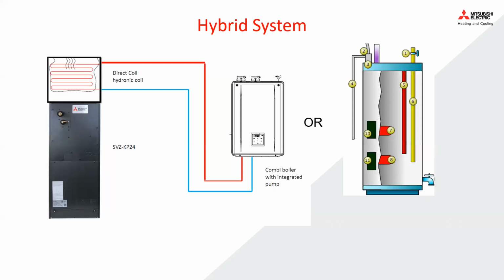So I have a builder up in Ottawa. This is their standard go-to, where they have a hydronic coil placed on top of a multi-position air handler. And so they happen to use a standard unit where it's not a cold climate, so it's only going to go back down to about negative 10. And then from there, the hydronic coil will take over. But again, we said Ottawa was 95% above negative 15. So really small amount of time that it'll be running on the hydronic coil.